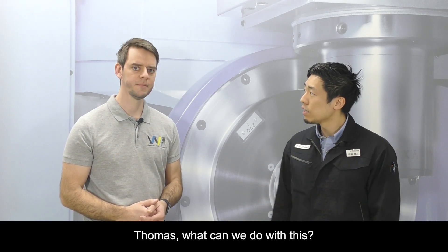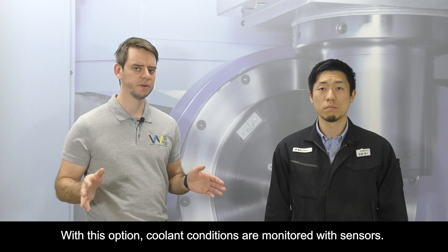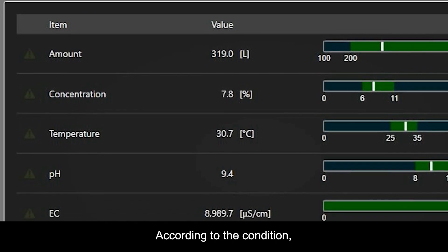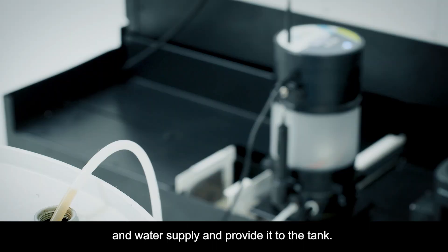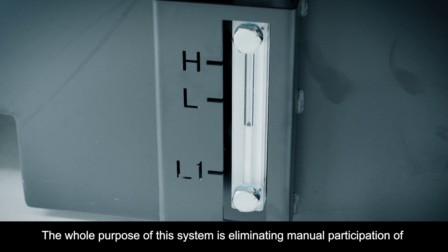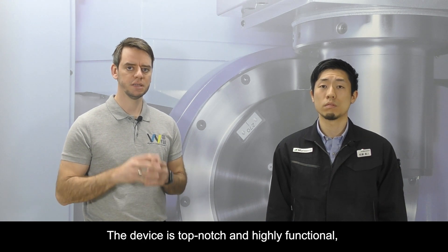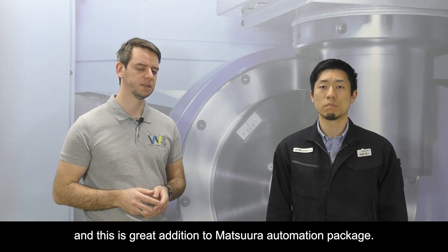Thomas, what can we do with this? With this option, coolant conditions are monitored with different sensors — for example, amount, concentration, temperature, and pH level. According to the condition, this system will automatically mix coolant out of a pail can and water supply and provide it to the tank. The whole purpose of this system is eliminating manual participation of an operator by automating coolant supply and its concentration management. The device is top-notch and highly functional, and this is a great addition to the Matsuura Automation Package.